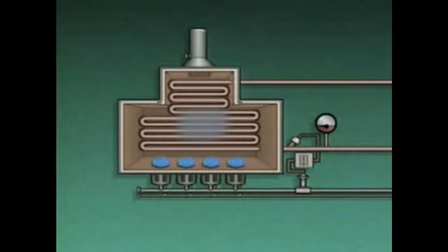Besides the drop in outlet temperature, the insufficient airflow can lead to another problem. If air in the furnace reacts with the unburned fuel building up in the furnace, the fuel may ignite away from the burners. This ignition may produce a positive pressure in the firebox. The positive pressure further impedes airflow into the furnace, making the original airflow problem even worse. This could cause even more unburned fuel to accumulate in the furnace. In addition, the positive pressure may cause flames to shoot out of the edges of the peephole doors or other furnace openings. Also, the igniting of fuel away from the burners may produce a pulsing or thumping sound.